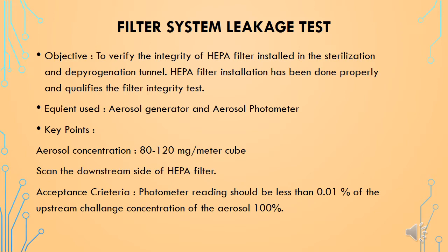To perform this test, place the aerosol generator to introduce an aerosol challenge to the filter in a zone-wise manner at a concentration of 80 to 120 mg per m³ of air, by opening the appropriate number of nozzles. Then with the aerosol photometer, check for leakages by scanning the downstream side of the HEPA filter, its perimeter, the seal between the filter frame and grid, and the structure including its joints.